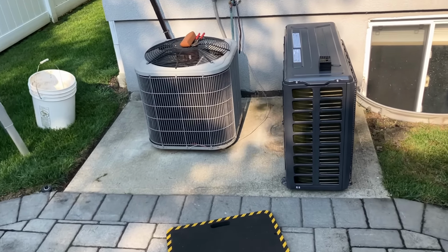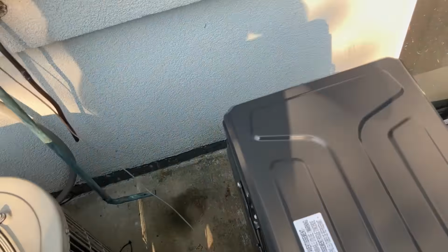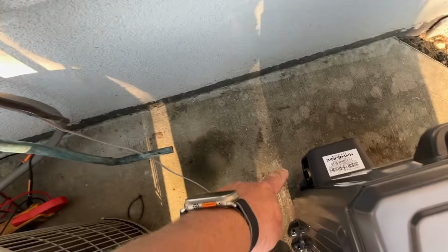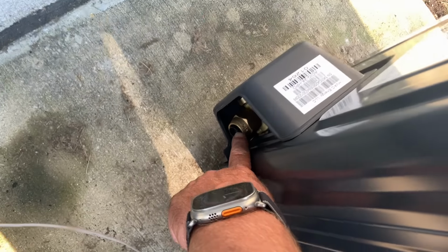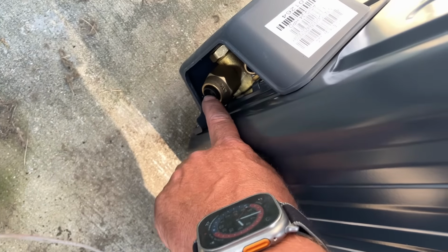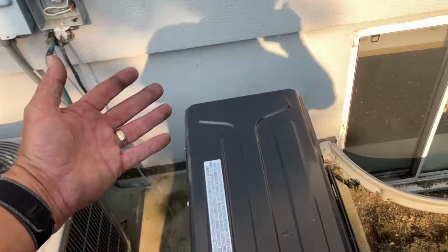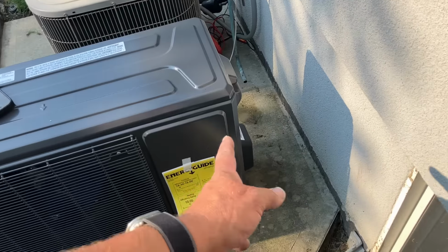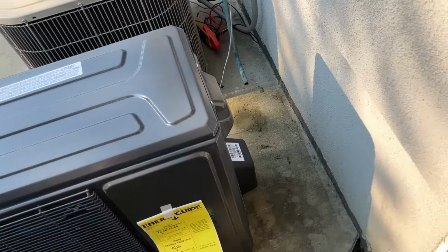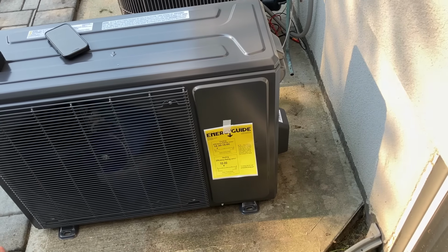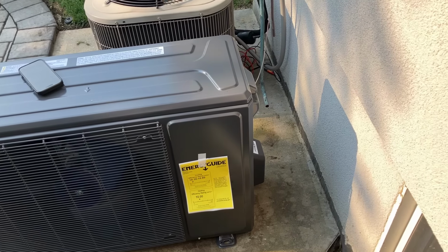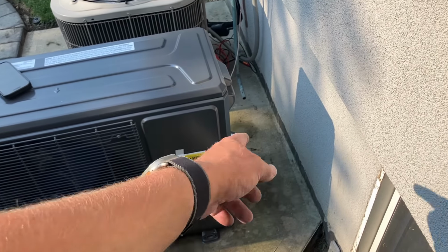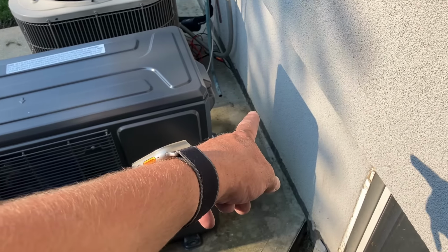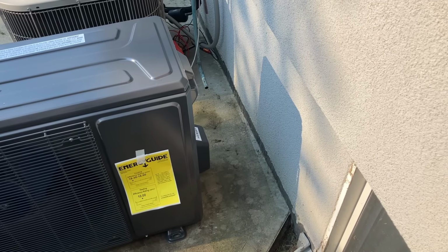Line set routing, we're going to figure that out next. I actually wanted to have this up against here and just beeline it with our 5/8 going to our 3/4 inch flare connection for the suction, and 3/8 right there. But then I RTFM'd, and I originally had like this much room, and I'm like, well wait, I'm not going to have any clearance there. Let me go to the manual, and I see it's 14 inches. I measured it - I'm going to keep it real, this is 12 inches, I'm just keeping it real. But we got plenty of room there.